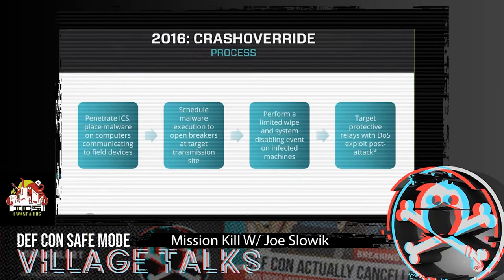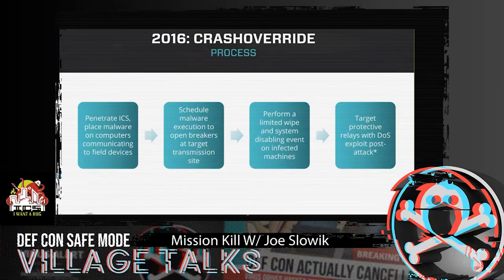The way this attack worked: first, penetrate the industrial environment and place malware on computers that can communicate to field devices controlling the breakers; then schedule that malware to open breakers at the target transmission site in a coordinated effort. There was also some after-effect — limited system wipe and disabling events on infected machines that induced the loss of SCADA control in the specific environment. Then there was a protective relay denial-of-service that took place post-attack, which becomes more significant when you look at this attack in terms of process dependencies.